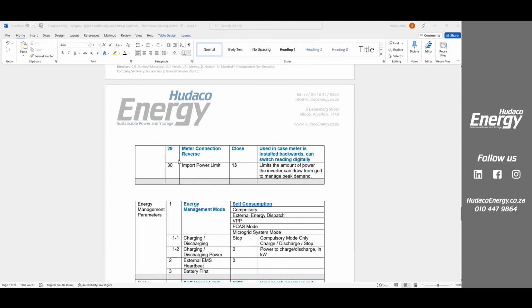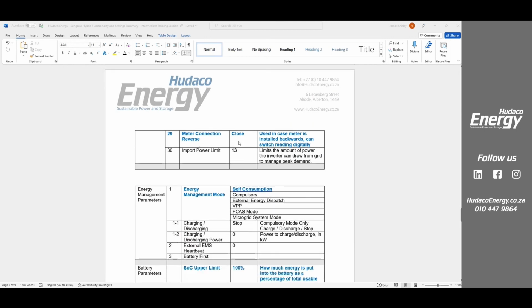Okay, this is a really, really cool feature. If you install your meter backwards or your CT backwards, you don't have to go to site to turn it around, right? Straight from the app, straight from your computer, whatever you do, you can log in. Oh, we might have reversed the meter. You can, well, it says close here, but you can just enable it. And what it'll do is it'll automatically swap the direction or it puts a negative in front of the value that it reads. And then your system will come live again.